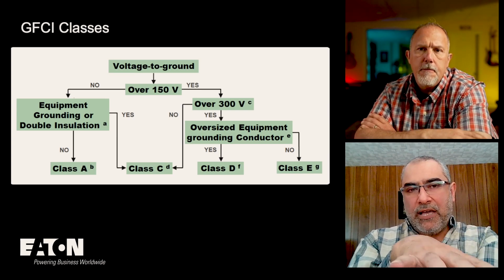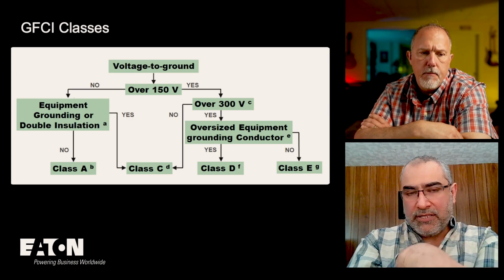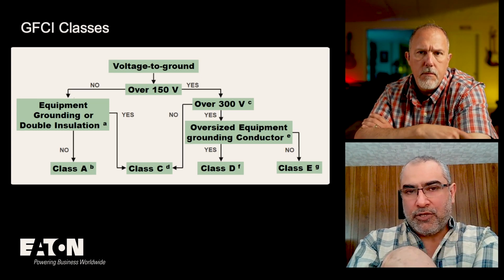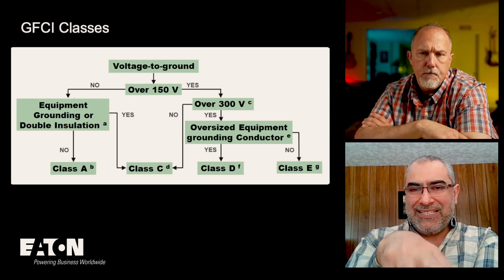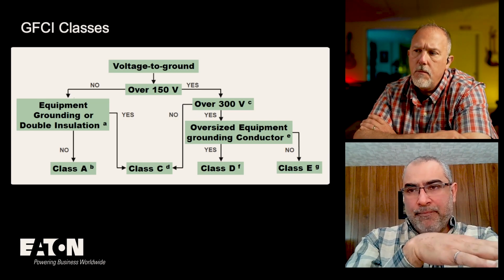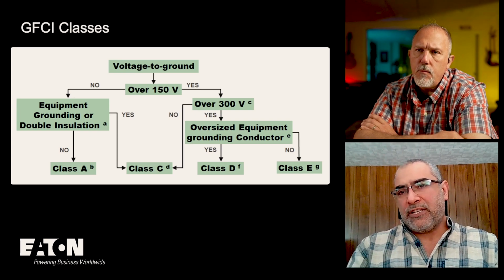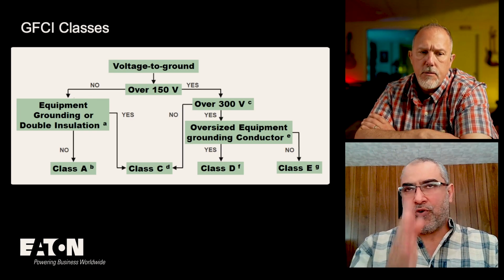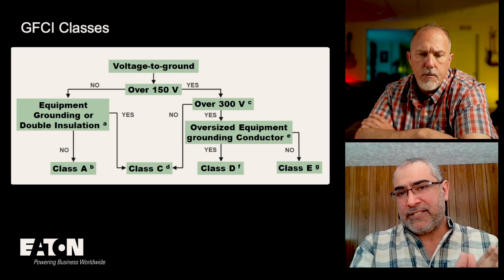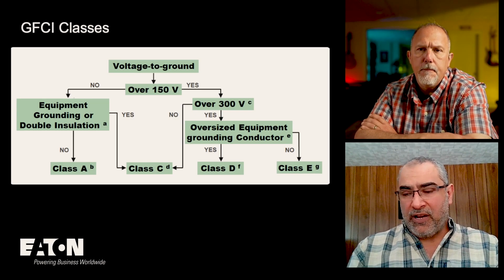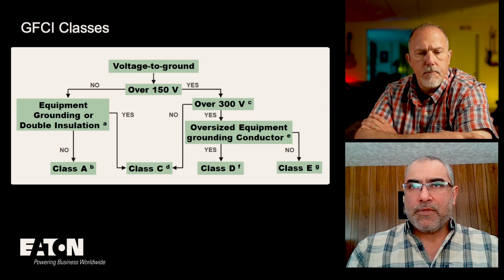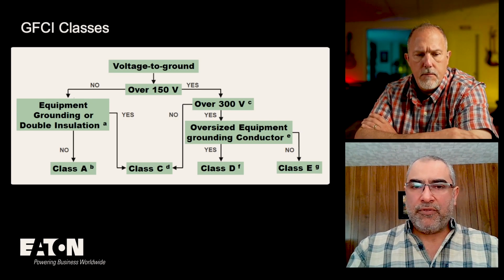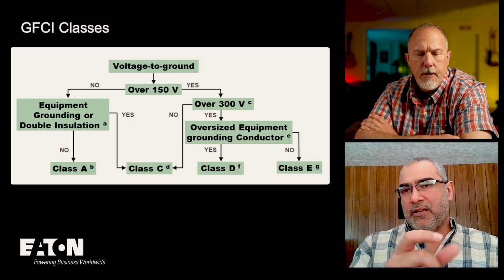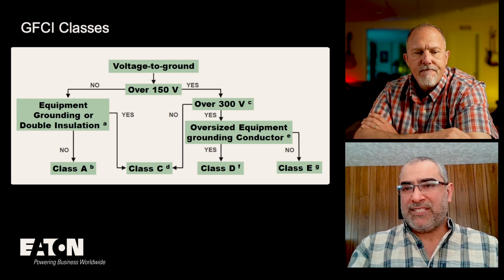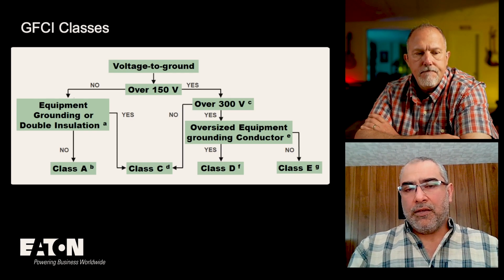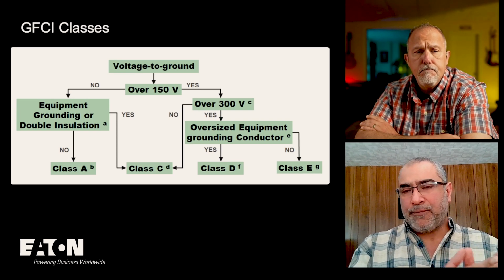Yeah. So this is how you classify the classes based on the voltage, but then the performance, like Tom was saying, it's interesting because for C, D, and E, it's 20 milliamp. So your trip threshold starts at 20 milliamp. And I know, Tom, there's a curve that we can show where you move the start point from 6 to 20 milliamp. Interestingly enough, for Class C there is an exception in 943C that says you can design Class C to start tripping at 6 milliamp, just similar to Class A. So it can be from 6 up to 20 milliamp.